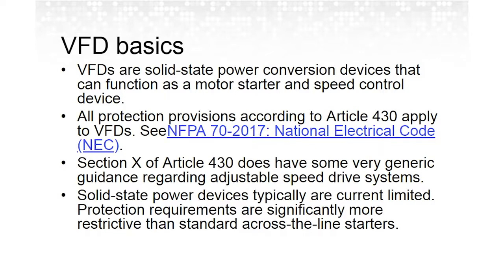The National Electrical Code does have a section within Article 430, basically Section 10, that applies to what they call adjustable speed drives, also VFDs, that provides some level of guidance regarding their specification and installation. However, it's still pretty vague. It needs a lot more development, and we'll probably see that as the use of VFDs becomes more expansive across the entire industry. But the big takeaway from Section 10, Article 430, is that totally enclosed fan cooled motors, those are cooled by a fan that's on the end of the shaft, if they operate at anything other than full speed, that fan is used for cooling.